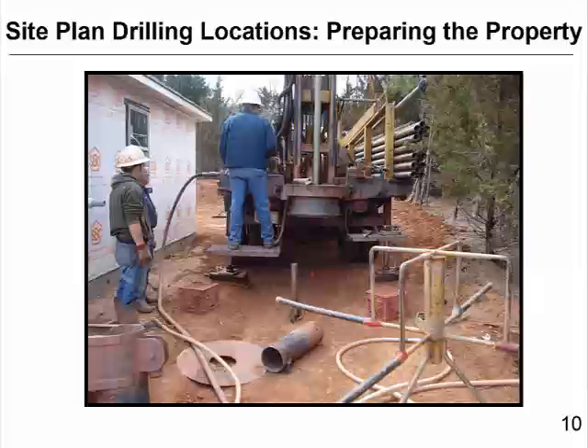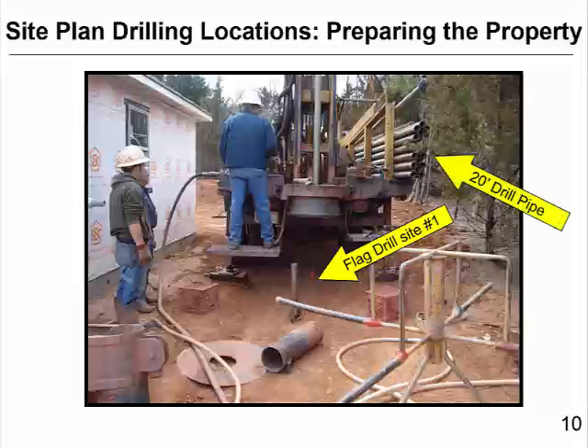This is the drilling location again, preparing the property, but you can see the different component parts there. There's a small flag there. That's all the drill sites were measured and located prior to drilling. And the drill pipe was marked off so that they wouldn't put more than 300 feet of drilling pipe in the ground. So they wanted to make sure that was right. So the rest of them were taped off so they couldn't be used. Mud ring was used, and then a short casing was used.